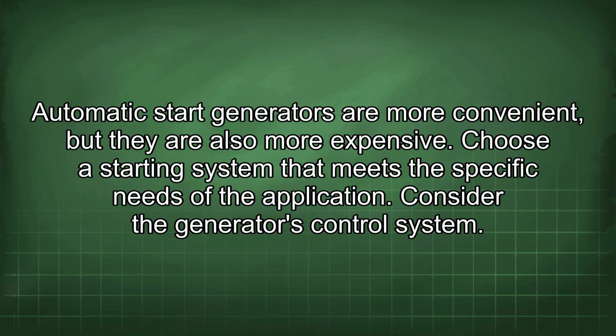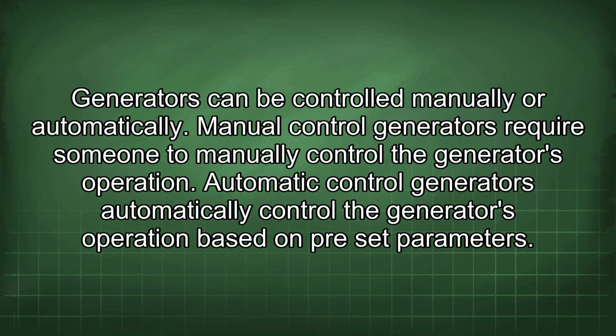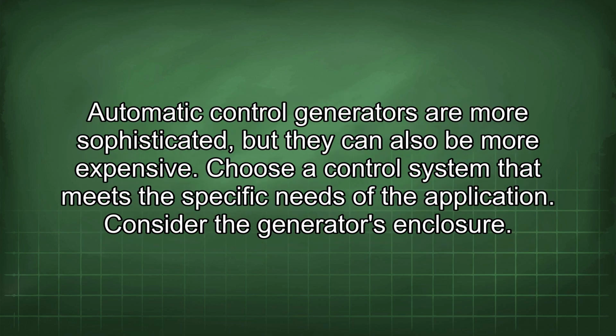Consider the generator's control system. Generators can be controlled manually or automatically. Manual controlled generators require someone to manually control the generator's operation. Automatic control generators automatically control the generator's operation based on preset parameters. Automatic control generators are more sophisticated, but they can also be more expensive. Choose a control system that meets the specific needs of the application.